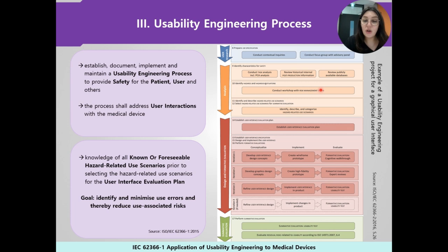Some, but not all forms of incorrect use are suited to control by the manufacturer. The usability engineering process is related to the risk management process, which includes the transport of the medical device, its storage, the installation, the operation, but also maintenance and repair and disposal.